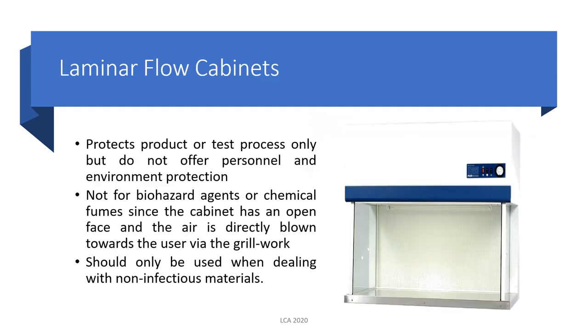The next type of cabinet is the laminar flow cabinet. This one protects only the product or the test process, but does not protect the personnel or the environment. This type of cabinet should not be used when processing chemical fumes or biohazardous agents, because it has an open face — it does not contain a sash as compared to the chemical fume hood and biosafety cabinet — which means personnel are directly exposed to air being blown through the grillwork. It should only be used when dealing with non-infectious materials.